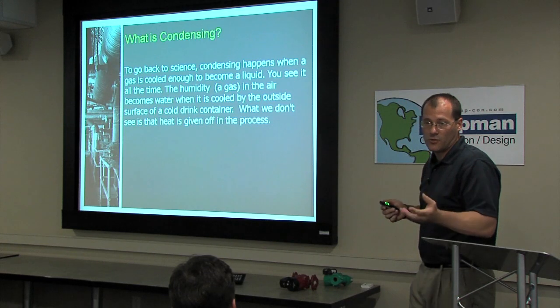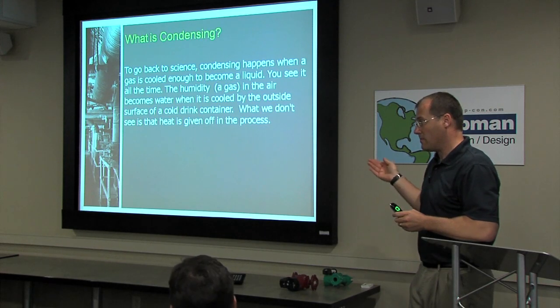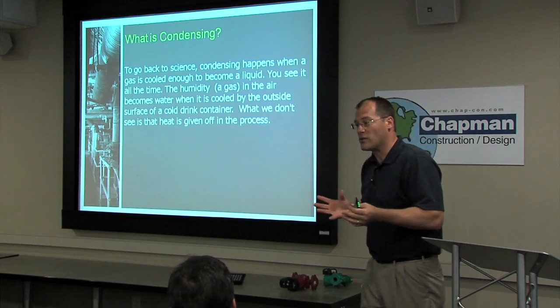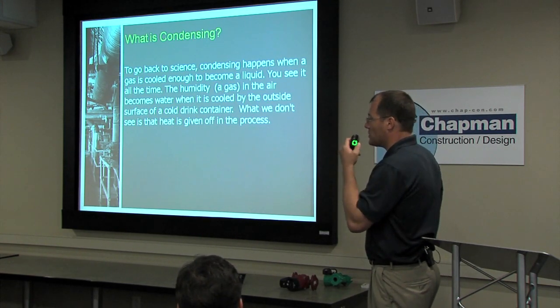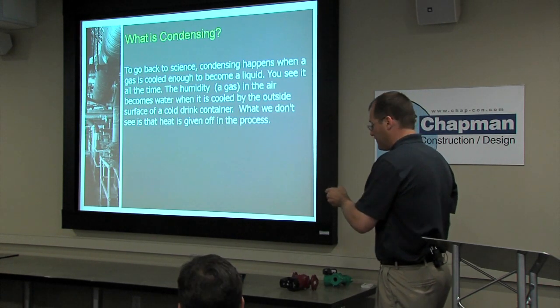But it takes a different heat exchanger material, one that can take that acidic condensate, and now you've got so little heat left in the flue gas, we can't go back up the chimney. If we put it in the chimney, we wouldn't create much of a draft. We would condense on the sides of the chimney. We would destroy the chimney. So now we vent directly to the outside in a material, PVC, CPVC, polypropylene, stainless steel, depending on the manufacturer, so that we can have condensation in that flue pipe, because it is going to collect there. So that's a big difference. When you hear about condensing boilers, just be thinking venting is an issue, and the material is going to change.